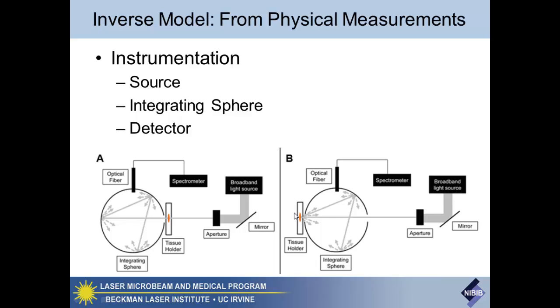Yeah. So the idea is that you don't want to have anything behind this because every single time you're illuminating the sample, you have transmittance and reflectance, and you only want to measure the one. If you have the transmittance, you want that to go off into space and not bounce off of something and interact with the tissue a second time. So if we put a black mat behind the tissue sample, it's good, if it's really black. Or free space, just let it fall off into free space. There are different ways of dealing with that, but it's always a tricky thing, because you want to just account for the light that interacts with the sample and enters the sphere. You don't want any other sources of light interacting with the sphere.